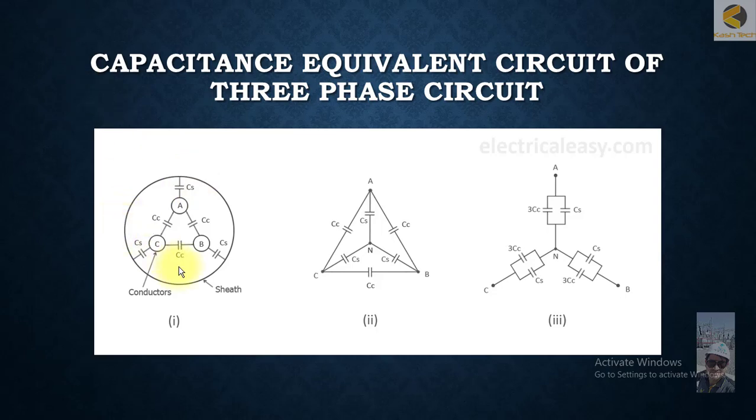Because mostly the circuits are three-phase: phase A, phase B, and phase C - these are basically three conductors, three cables. There will be capacitance between conductor A and conductor B, conductor B and conductor C, and then conductor C and conductor A. Also, this is the sheath of the cable, which is also a conductor.